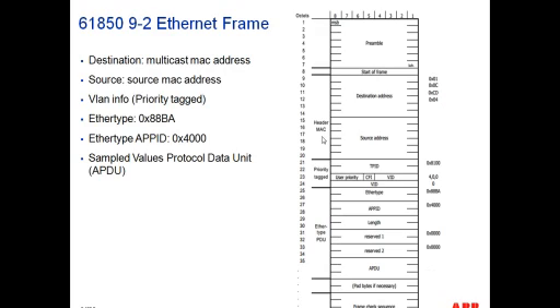Are VLANs supported? Just from a technical perspective, when we talk about the 61850 sample values protocol, based on the implementation guidelines of the UCA group, we're limiting ourselves to 4 currents and 4 voltages. There are no trip signals that you can embed in that datagram. For that, you would need to use 61850-8-1 in the form of GOOSE messages.